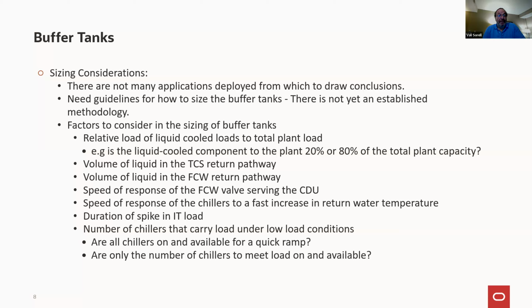because it's much more of a complicated issue, because the factors that go into the sizing of a buffer tank have to look at how much of the load in the entire plant that the plant serves is actually a liquid cooled load. If it's 20%, it probably doesn't matter all that much, because if you have that spike in that 20% load, by the time it mixes with the 80%, it's not going to amount to that much. And you probably don't need a buffer tank under those circumstances.